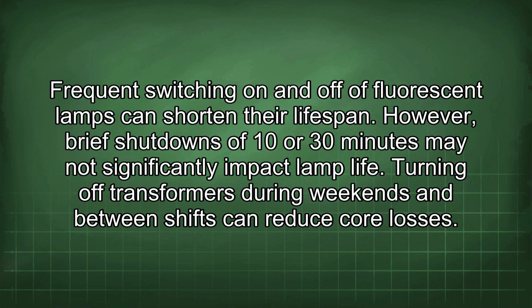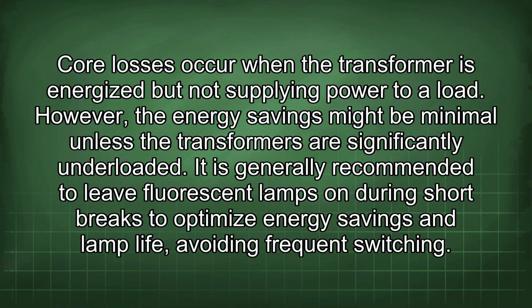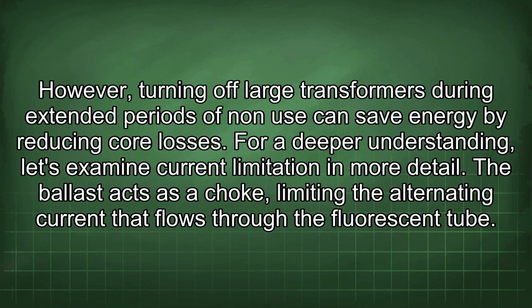Turning off transformers during weekends and between shifts can reduce core losses. Core losses occur when the transformer is energized but not supplying power to a load. However, the energy savings might be minimal unless the transformers are significantly underloaded. It is generally recommended to leave fluorescent lamps on during short breaks to optimize energy savings and lamp life, avoiding frequent switching. However, turning off large transformers during extended periods of non-use can save energy by reducing core losses.